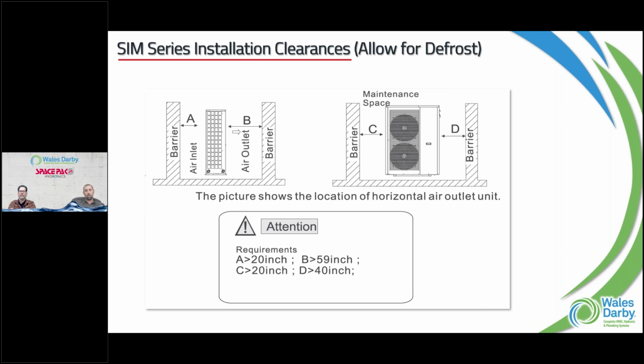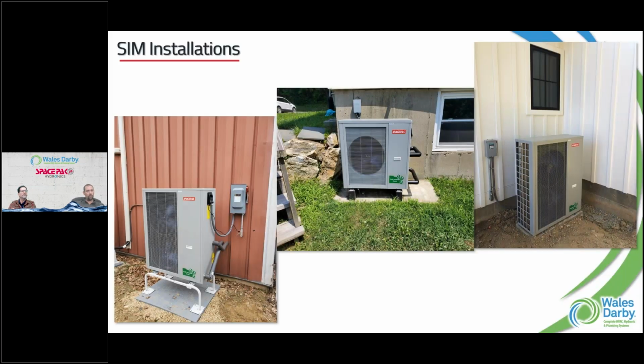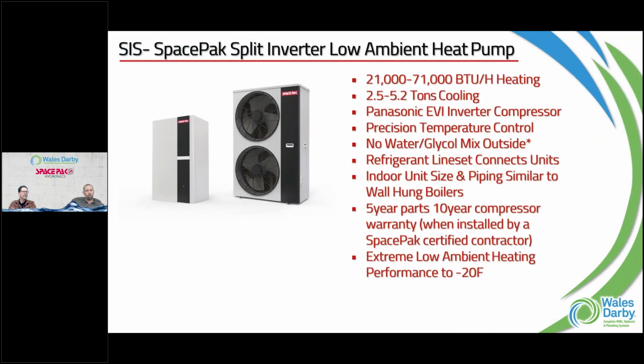So also being heat pumps, right? We talk about defrost. There's going to be a cycle. There's going to be condensate around that outdoor unit. So we want to make sure that thing's up off the ground and we're not trapping any refrigerant or any water in there, and having a refreeze or something like that. So follow the installation manual. You'll find a lot more of these dimensions. Look at some of the sims and some good applications. That one's on the ground because I believe it is covered. So pretty cool stuff there.